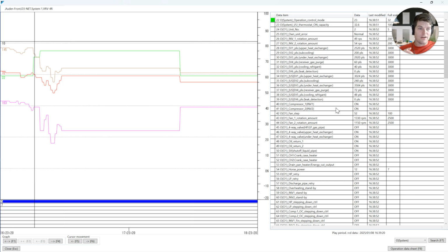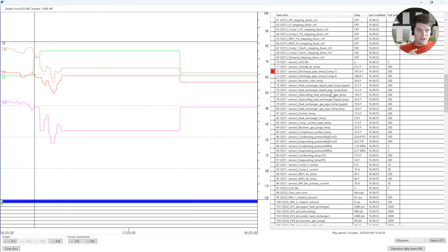And I'll set a timer if I have to. Less than 60 seconds, I can check all 4 of these four-way valves. Say that 5 times fast. I can check all 4 of these four-way valves extremely fast and not have to go out to an outdoor module or look at anything.